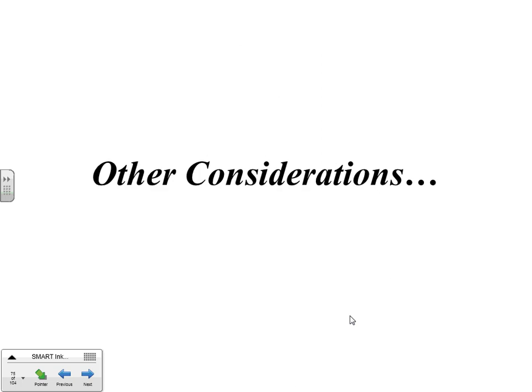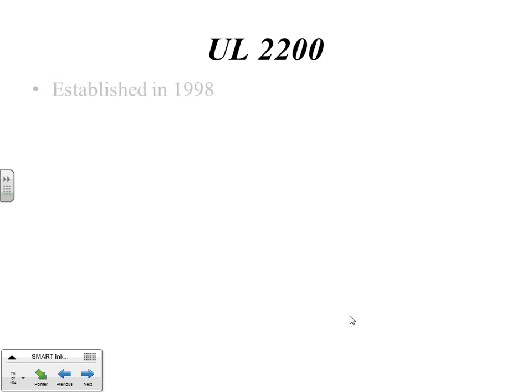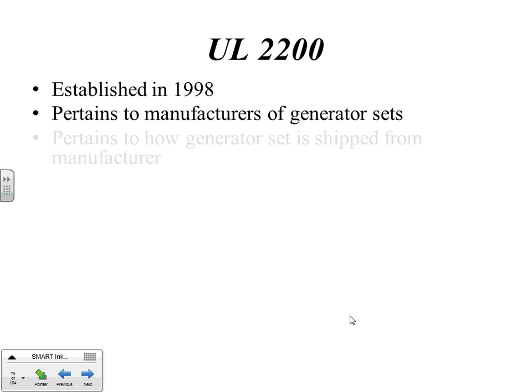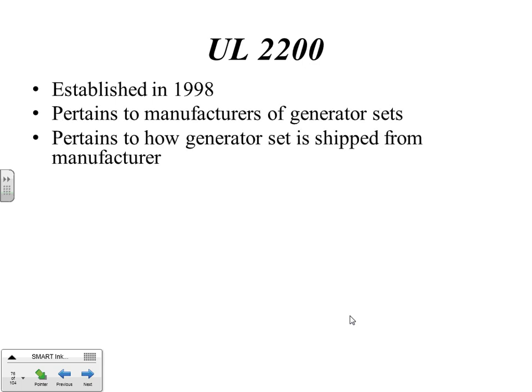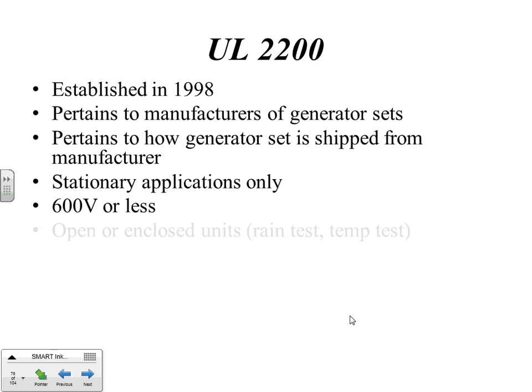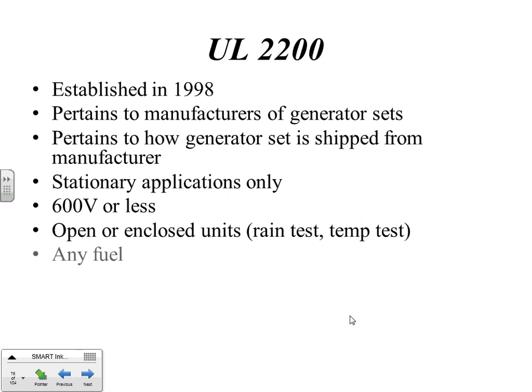Other considerations. When we design a system, there's a lot of things we have to think about. UL 2200. This was a UL listing for generator sets that came into play in 1998. It pertains strictly to the manufacturers of the generator sets, and it tells how the set is going to be shipped from that manufacturer. It's for stationary applications only. In other words, no mobiles, municipal sets, that kind of thing.